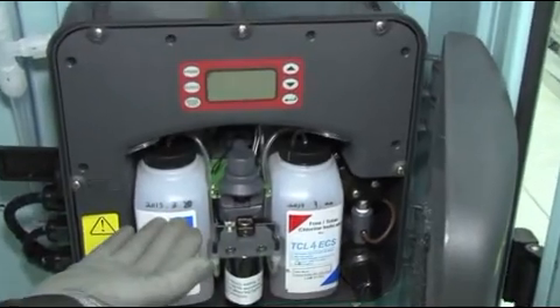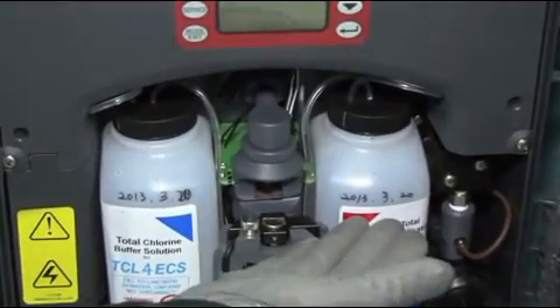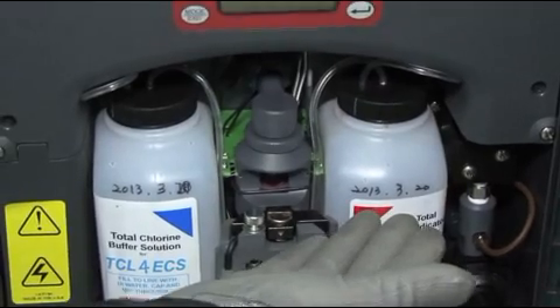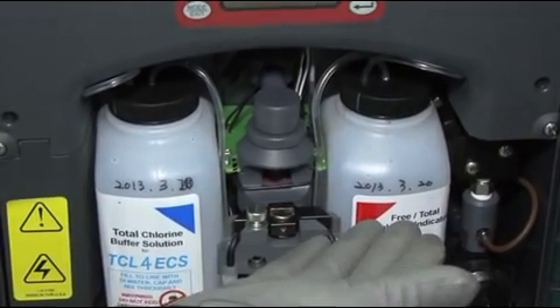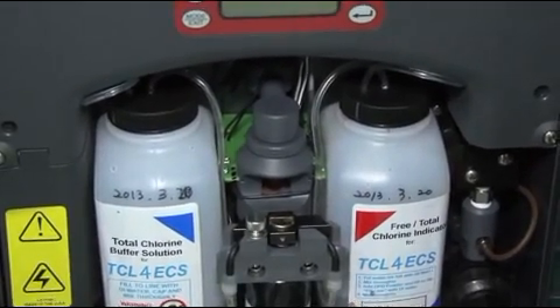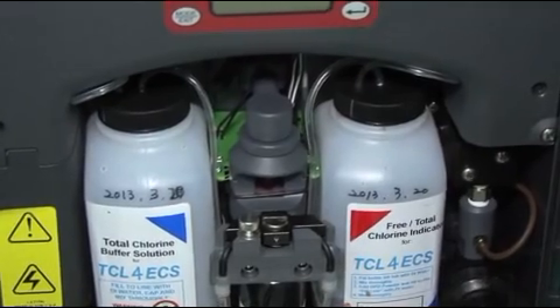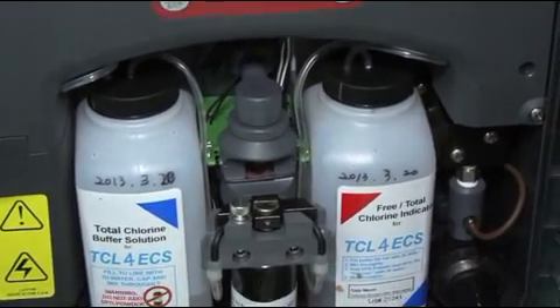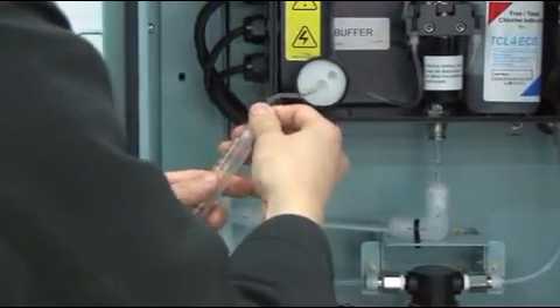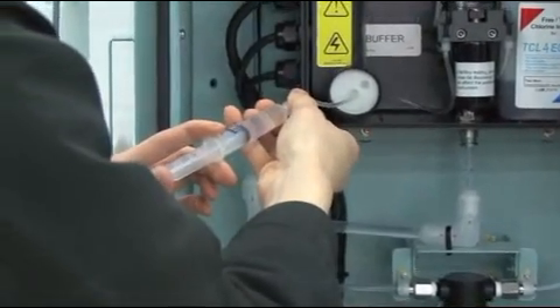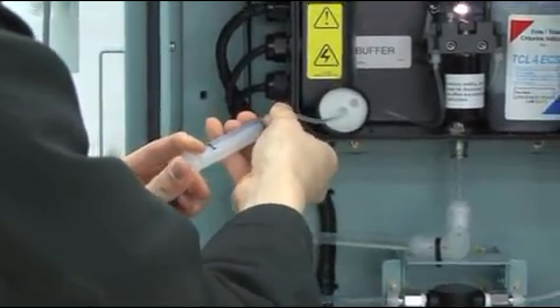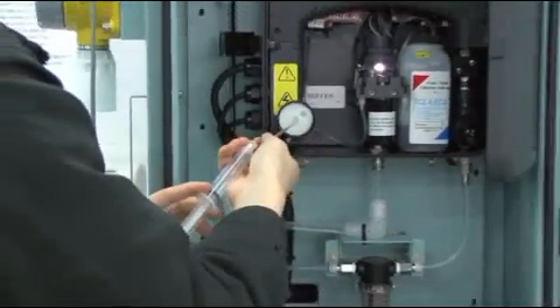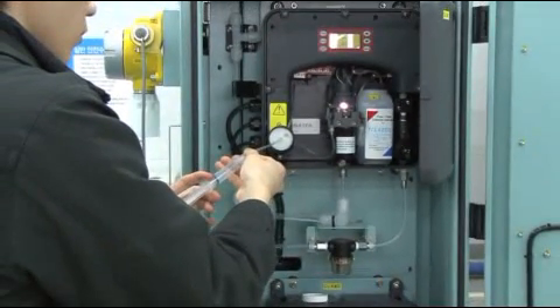2. When the same problem persists even if sampling water flows into the sensor. 1. Check replacement date of TRO sensor. Please refer to checkpoints before operation selecting remote mode and checking supplies. Step 3. 2. Make sure to prevent air coming into the tube between CLX and the sensor when replacing the solution. Please refer to replacement of supplies, replacement of CLX reagent. If the same problem persists, please contact the manufacturer.